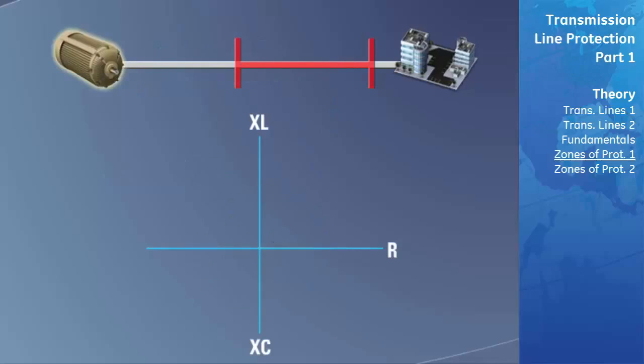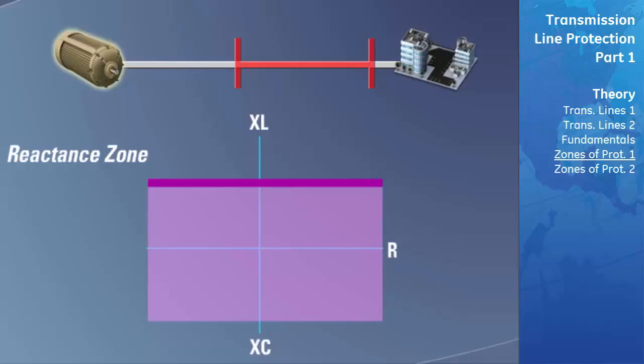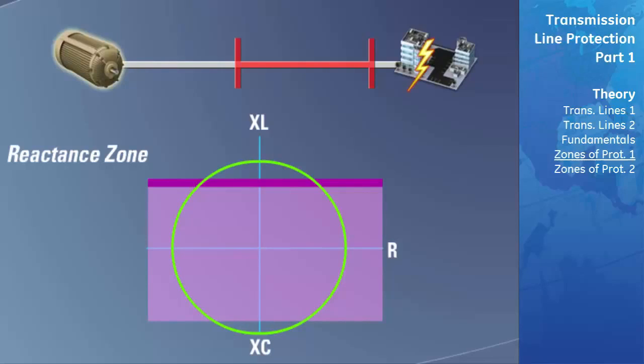The zone of protection known as a reactance zone is used to detect when the impedance of the fault has a very high resistive component. If the fault does have a high resistive impedance, this indicates that there is a load on the transmission line and the fault is most likely not on the transmission line. This type of zone is usually never used to trip a transmission line on its own but is normally used to supervise another distance zone of protection. For example, if an impedance zone detected an impedance entering its zone due to an external fault, the reactance zone can block the impedance zone from tripping because it can determine that the impedance is mostly resistive.